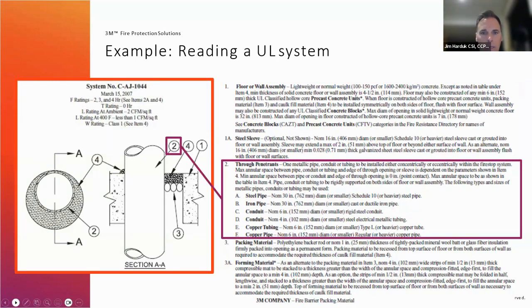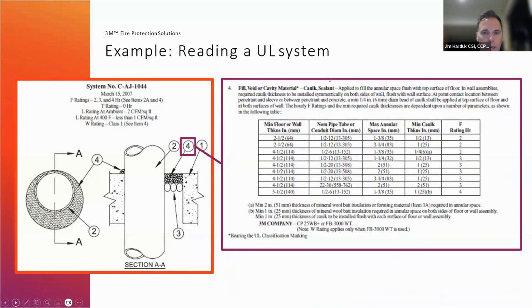Next slide, please. All right. And then at the bottom of the system drawing, as I had mentioned before, sometimes there's a matrix which shows the attainable hourly ratings. For this particular system, you have options for 2, 3, and 4 hour. And it tells you what the diameter of the through penetrants can be for the corresponding hourly rating.